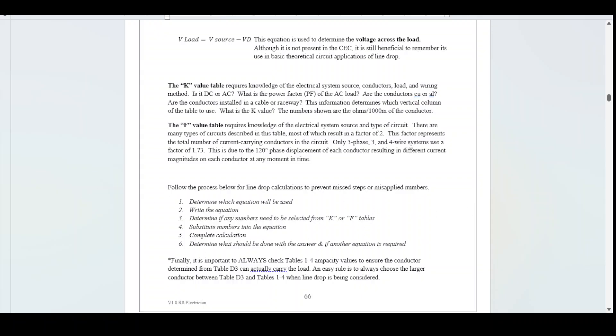Follow this process for line drop calculations to prevent missteps. Step one: determine which equation will be used. Step two: write the equation. Step three: determine if any numbers need to be selected from the K or F tables. Step four: substitute numbers into the equation. Step five: complete the calculation. Step six: determine what should be done with the answer and if another equation is required. It's important to always check tables 1 to 4 ampacity values to ensure the conductor determined from table D3 can actually carry the load. Always choose the larger conductor from table D3 and tables 1 to 4 when line drop is being considered.